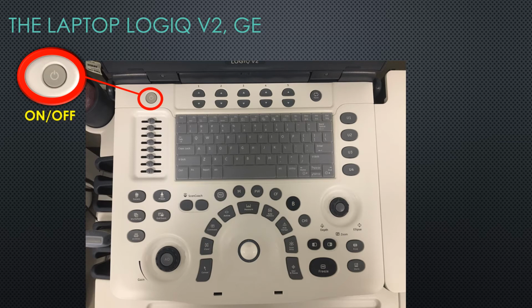Typically on a laptop machine of any sort, you'll have patient information and presets. Patient information is because you want to set up your scan first as one of your order of operations. And the presets are kind of like getting you close, right? So we know we want to do shoulder scans, and it will set the depth and the brightness and all of those components to be what you might need for a shoulder scan or a knee scan. So presets will get you close, but you still need to fine-tune the settings of the machine to get the best images that you can with every image you take.